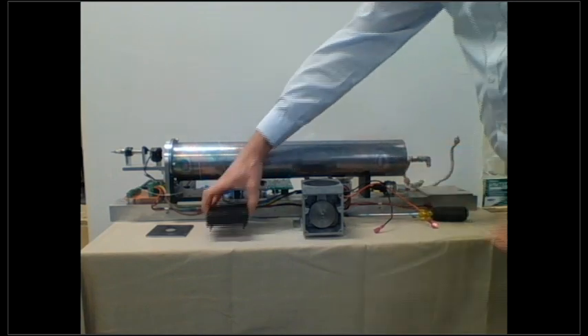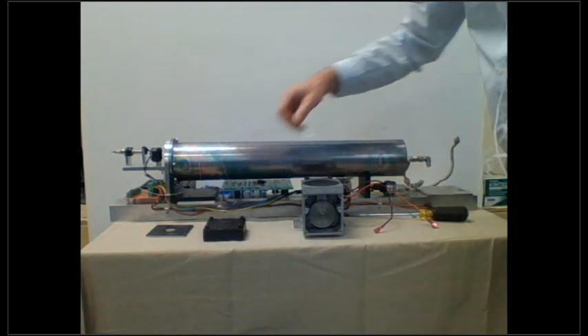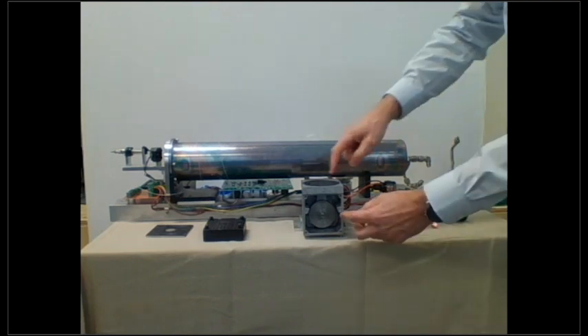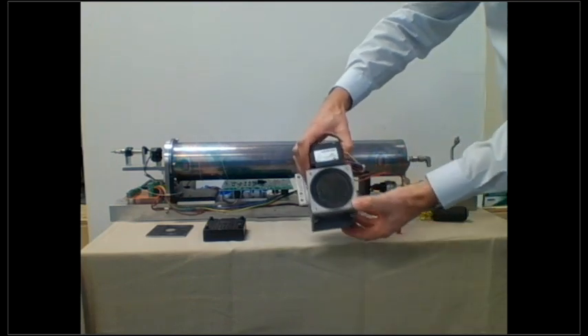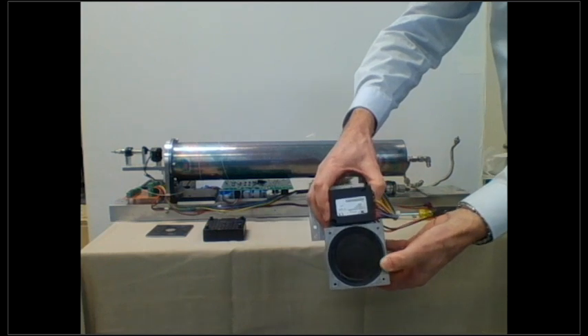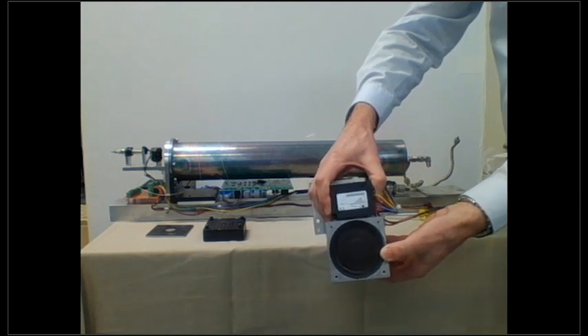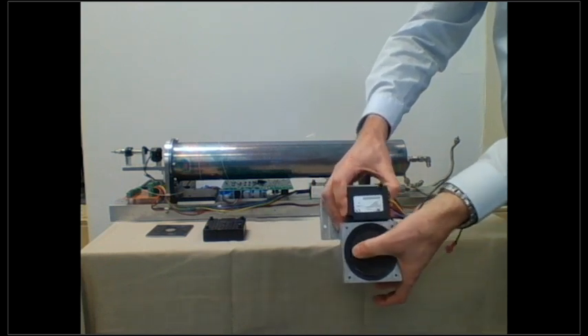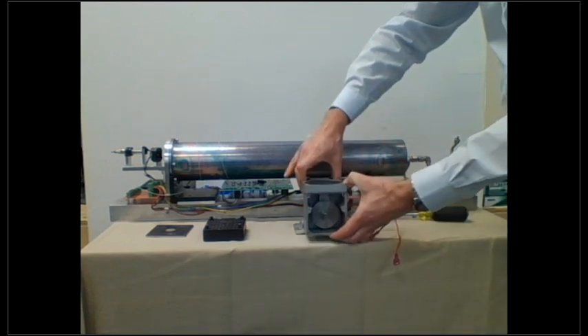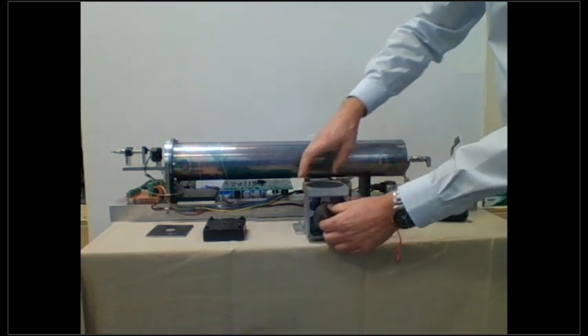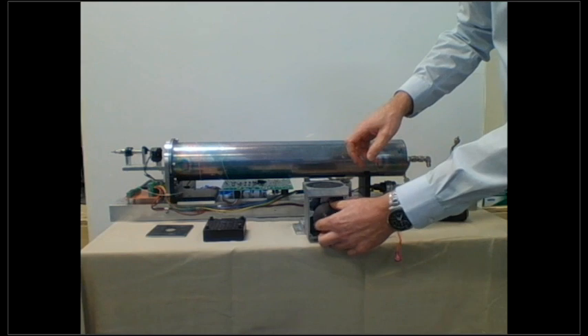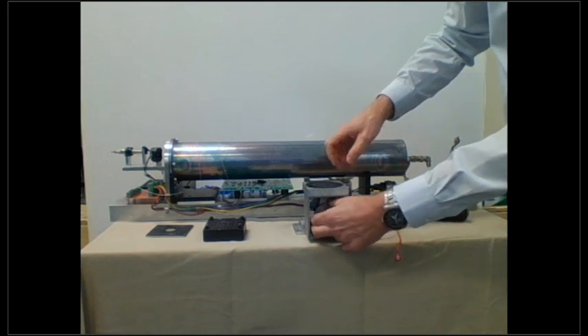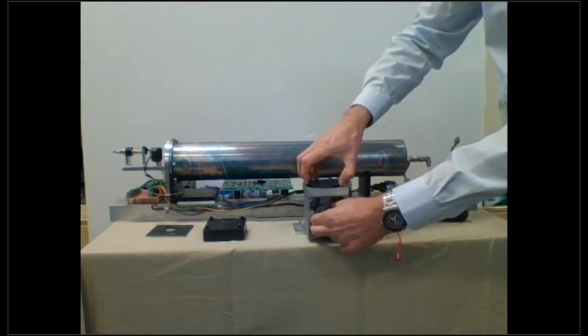The diaphragm itself is here. So you can see actually this one's been fairly well used and abused. It's got a little bit of a tear in it, so it needs to be replaced. To get access to the diaphragm, you simply turn the rotor and get the piston in such a position that it gives you access to the diaphragm, and then you can simply grab it and turn it. It's on a screw.